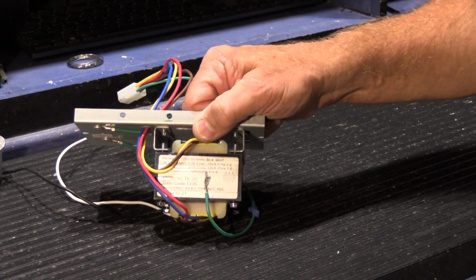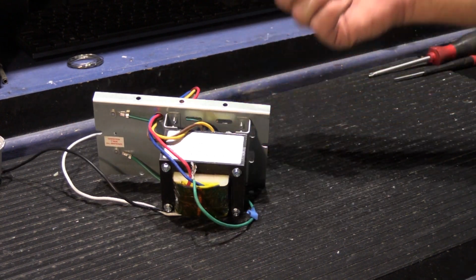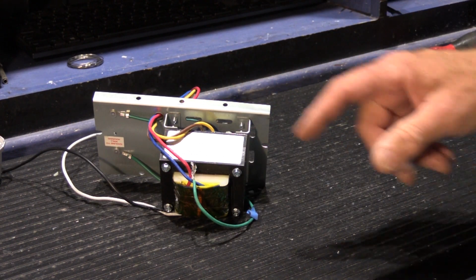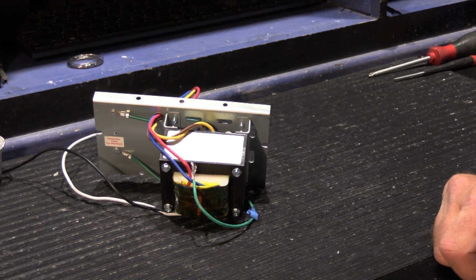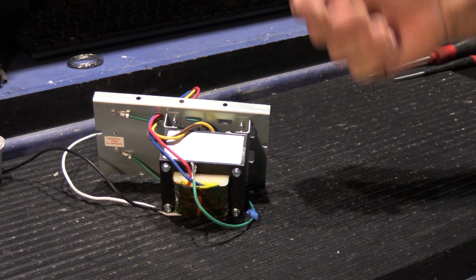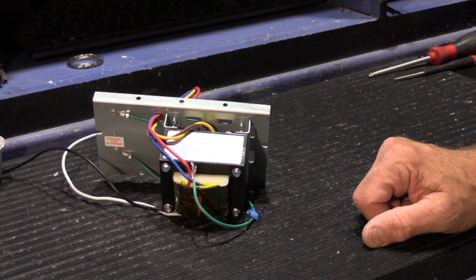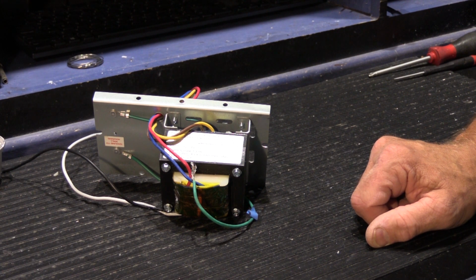It's all put back together. We know it's good now. We replaced the input fuse on the primary side of the transformer, and it's alive again. So that's how you fix the blown fuse on a NuTone NM series or Music and Sound DMC series low voltage transformer.